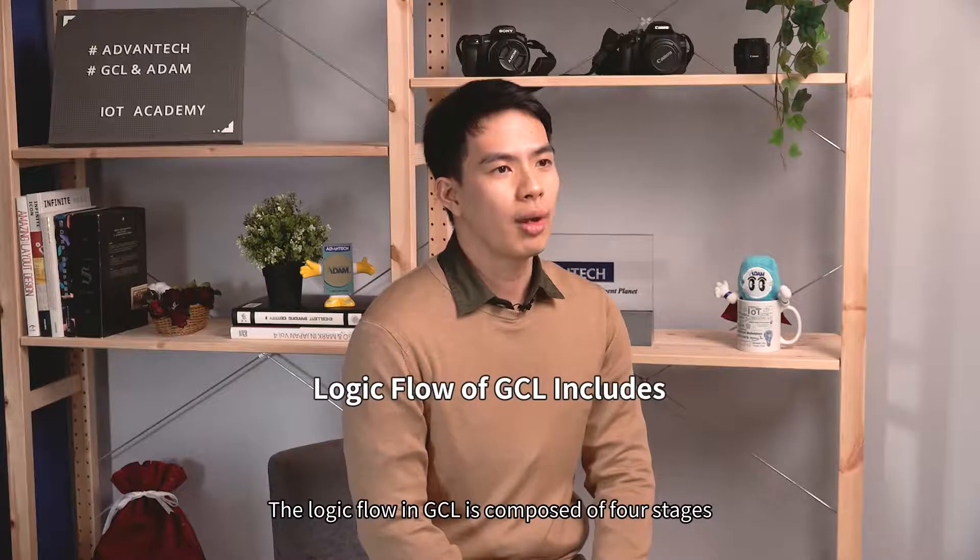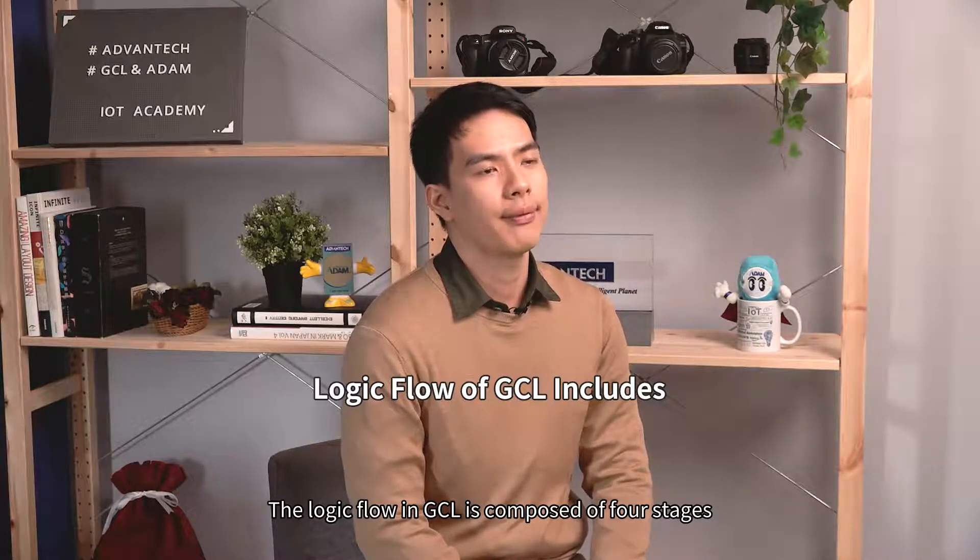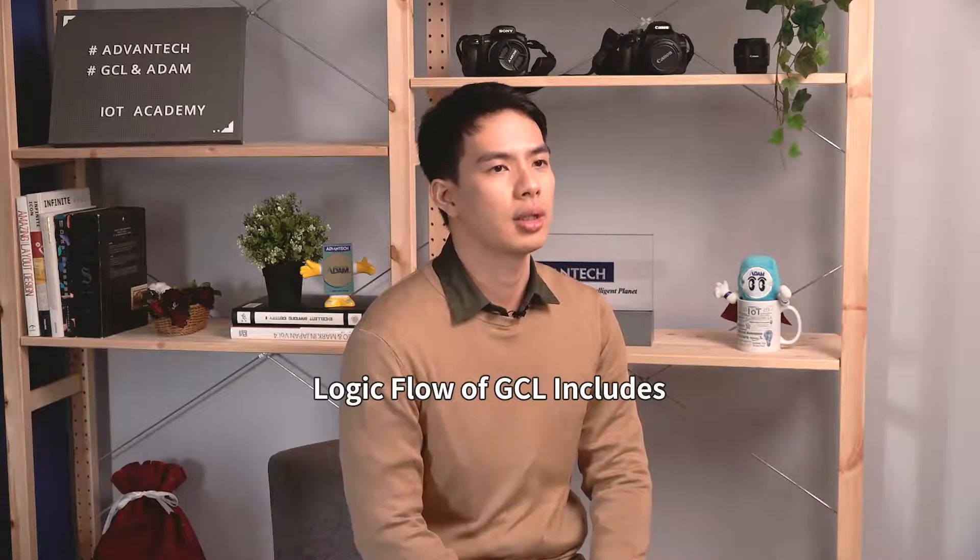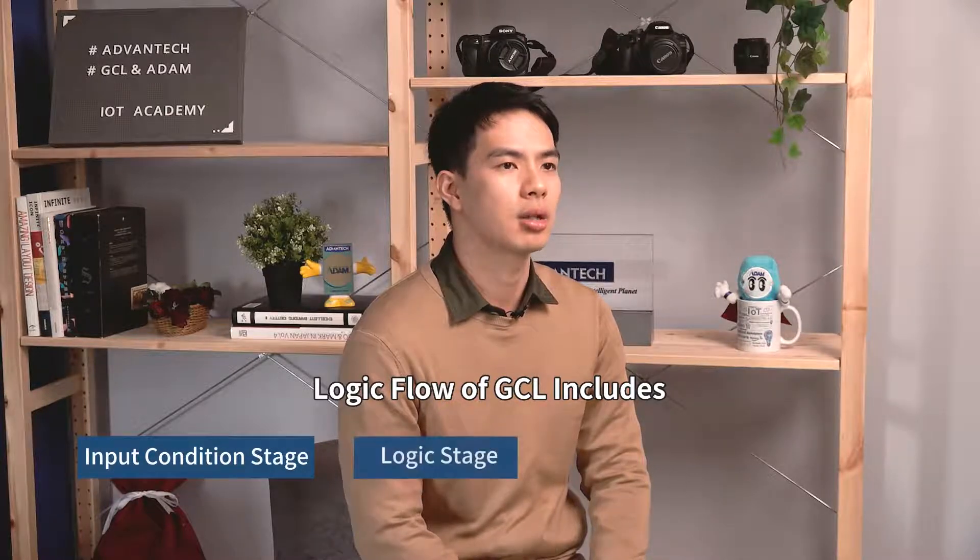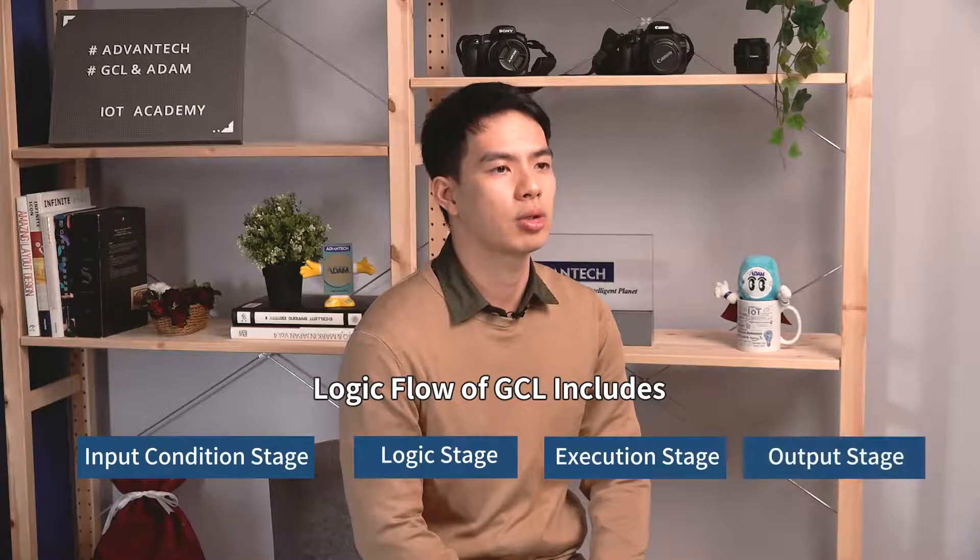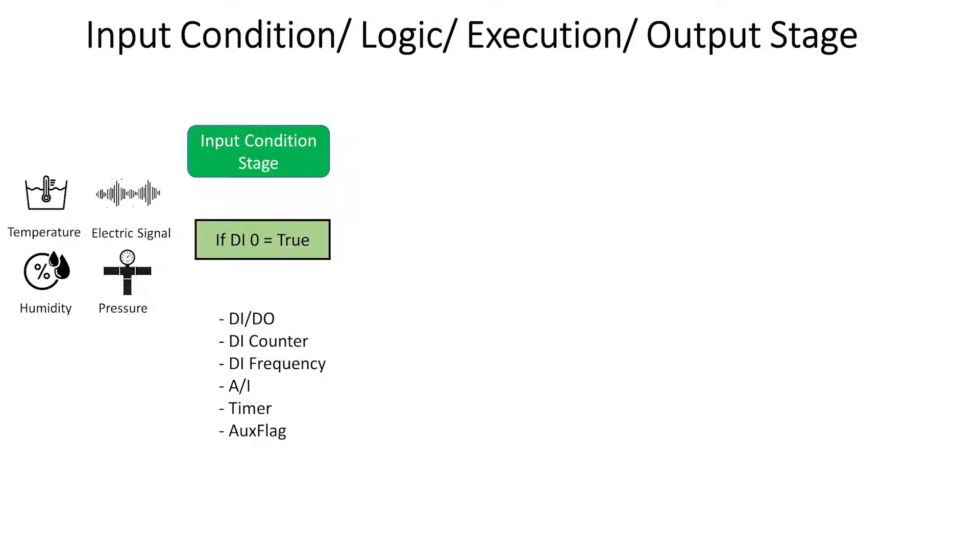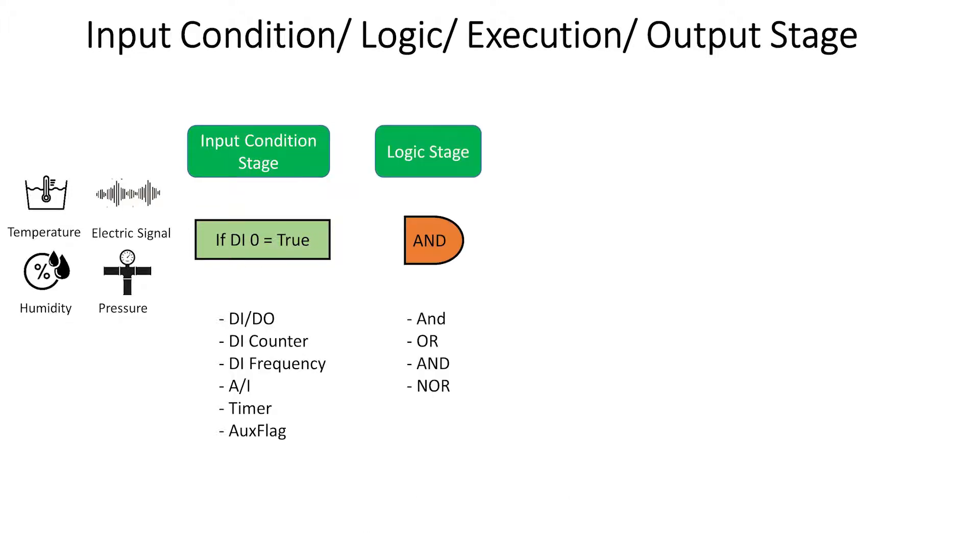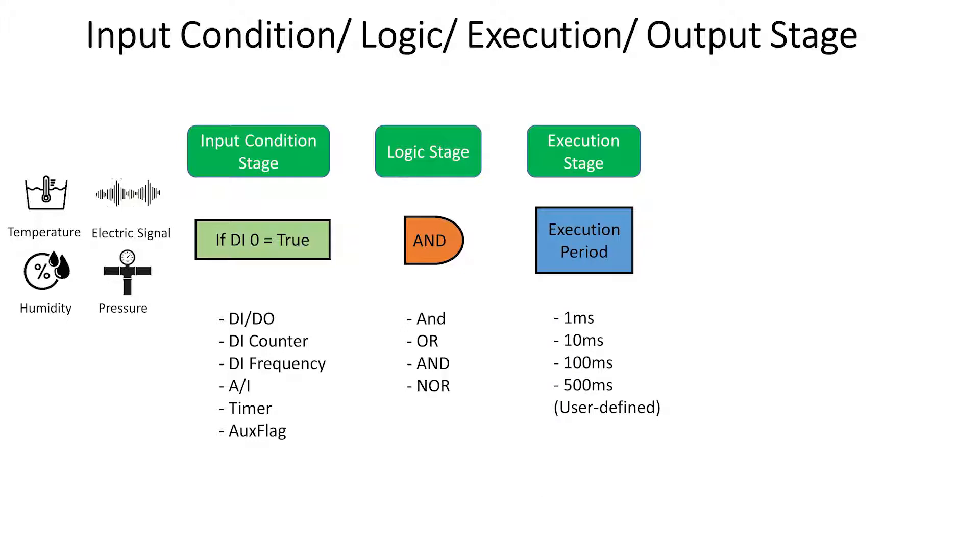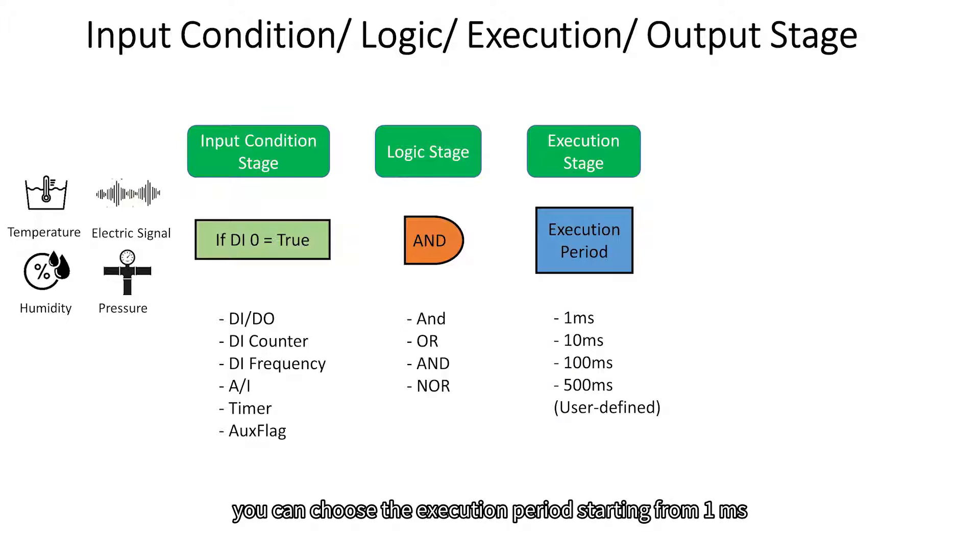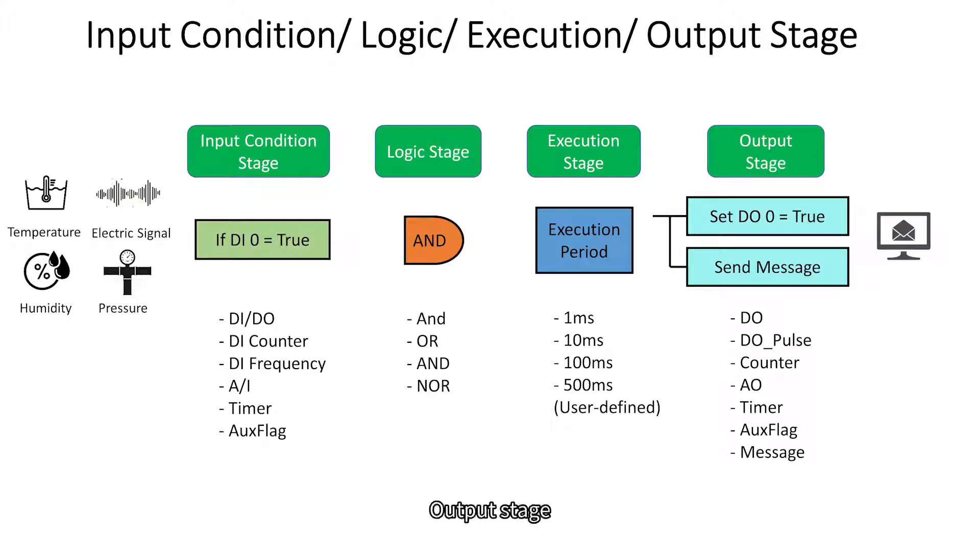The logic flow in GCL is composed of four stages, including input condition stage, logic stage, execution stage, and output stage. First, input condition means a logic condition decision based on the input data. It can be logic true or false. Second, logic. There are four types of logic gates: AND, OR, NAND, NOR. Third, execution. You can choose the execution period starting from one millisecond. Fourth, output stage. There are a few output types you can choose. Let's set DO to true to turn on the light or send message.